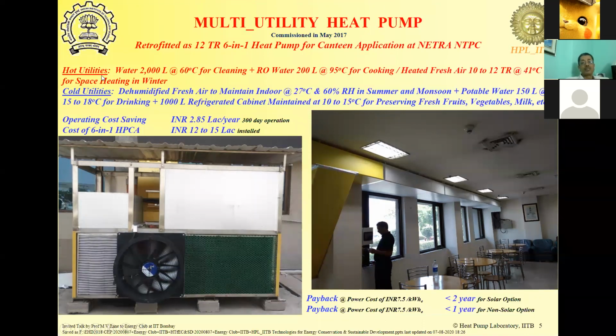The primary utility that this produces is air conditioning. Let me first start with that. It gives you dehumidified fresh air and maintains the indoor at 27 degrees and 60% RH in summer and monsoon. It also gives hot air at 41 degrees in winter in order to maintain the space temperature of 22 to 24 degrees centigrade in winter in the canteen. It concurrently generates 150 liters of potable water. The potable water is stored within this tank, within the heat pump itself. So there are no pumps required to circulate the water. There is no separate heat exchanger required for that, and so on. And we can deliver potable drinking water at 15 to 18 degrees centigrade at the outlet of the tap without using any pumps in this particular situation.